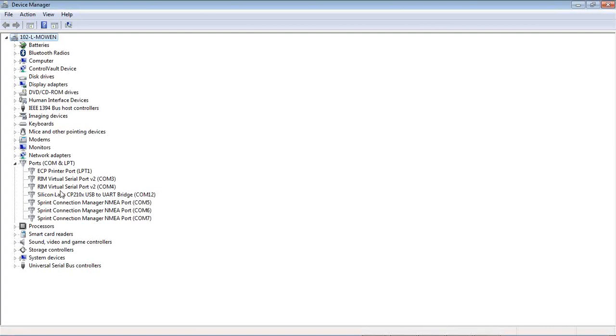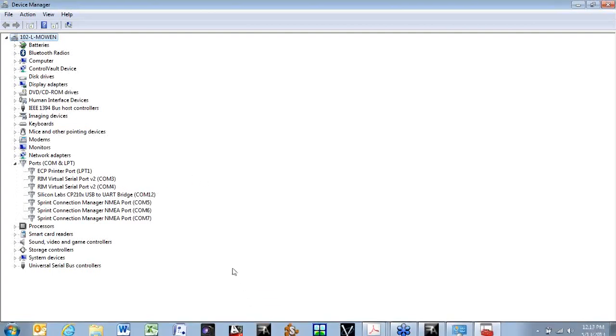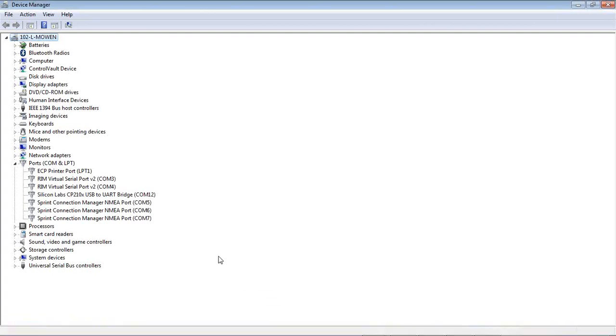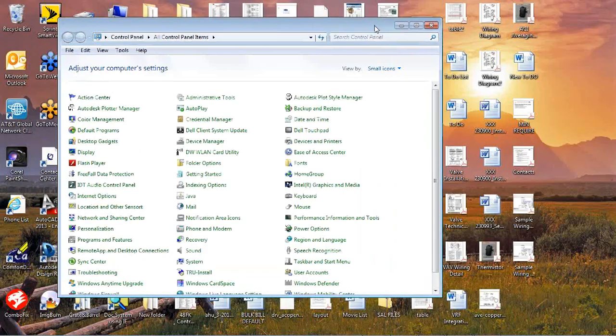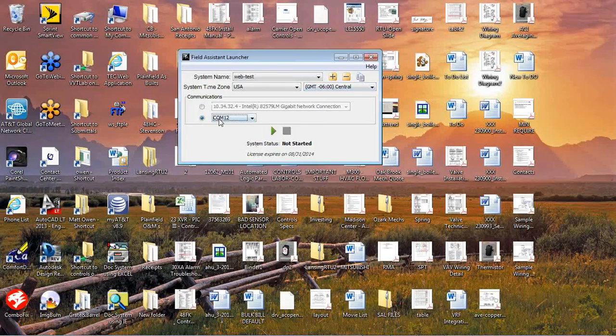So when you first start up your Field Assistant, you want to select the port that you're plugged into. You can go to Device Manager and double check to see which COM port you're plugged into. Right now I'm in COM 12. Now that I've confirmed that, I want to go back to my Field Assistant. I would select COM 12. Once I have my COM port selected, my database set up, and my time zone set up, I'm going to hit this green play button.